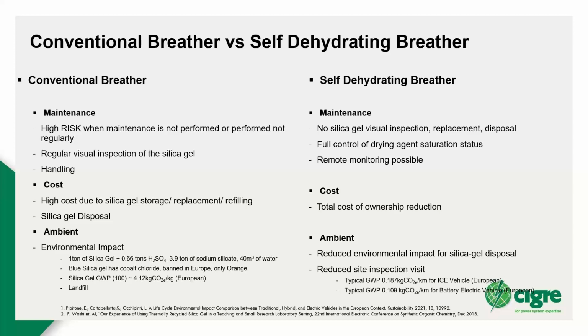So if you have 1 transformer with 10 kgs of silica gel and do a 6-monthly replacement, every year you need around 20 kgs. If you have 100 transformers in your fleet, that's 2 tons of silica gel every year, and if you repeat this for 30 years, you'll need around 60 tons. That 60 tons, in a life cycle assessment, translates to almost 240 tons of carbon dioxide. So there is an environmental impact.